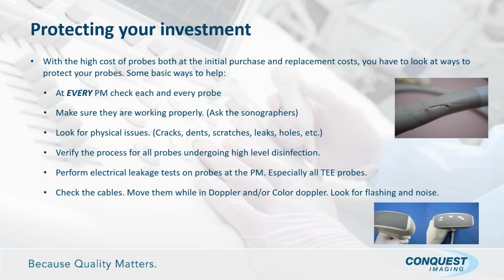So what's the best we can do? I'm not going to blow you away here with anything that's super new. I've had other colleagues, other companies in the industry saying this for years, and honestly, I still don't see it happen like it should, but there are ways you can protect your probes. And a lot of it's just basic. When you're doing a preventive maintenance check, you've got to look at every probe and do a very good physical examination. Make sure they're working. Ask the sonographers if there are any problems. But it's really about catching these problems beforehand. Again, looking at physical issues, like I said, pinholes and leaks and so forth.